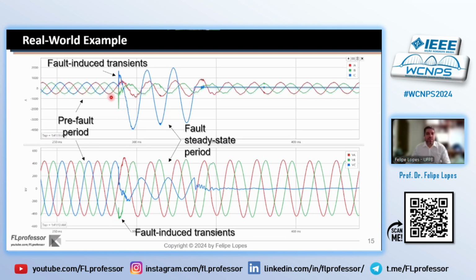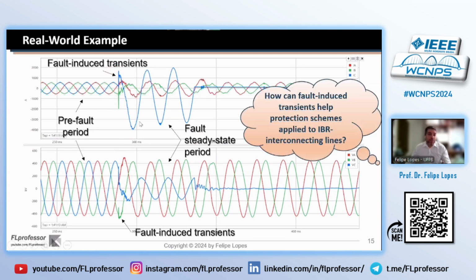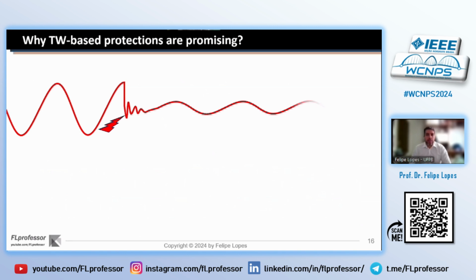As you can see, they take place in a very narrow time window, and the question is now, how can these transients help protection schemes applied to IBR interconnected lines? So to understand that, let's see how the controllers and the system behave during a fault. If a fault takes place, there will exist a step surge on the voltage at the fault point. It will generate some transients and launch traveling waves over the system.